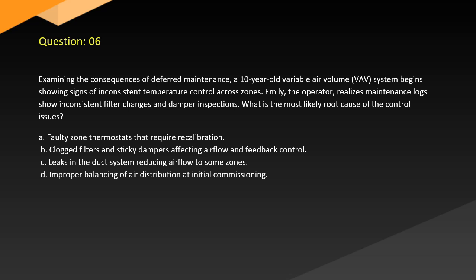Question 6. Examining the consequences of deferred maintenance, a 10-year-old variable air volume (VAV) system begins showing signs of inconsistent temperature control across zones. Emily, the operator, realizes maintenance logs show inconsistent filter changes and damper inspections. What is the most likely root cause of the control issues? A. Faulty zone thermostats that require calibration. B. Clogged filters and sticky dampers affecting airflow and feedback control. C. Leaks in the duct system reducing airflow to some zones. D. Improper balancing of air distribution at initial commissioning.